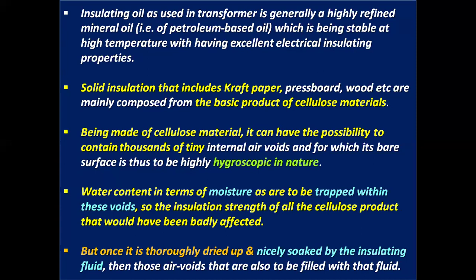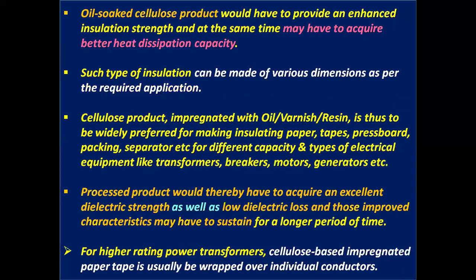Water content in terms of moisture is trapped within these voids. So the insulation strength of all these cellulose products is badly affected. But once it is thoroughly dried and nicely soaked by the insulating fluid, those air voids are filled with that fluid. Oil-soaked cellulose product provides an enhanced insulation strength and at the same time acquires better heat dissipation capacity.